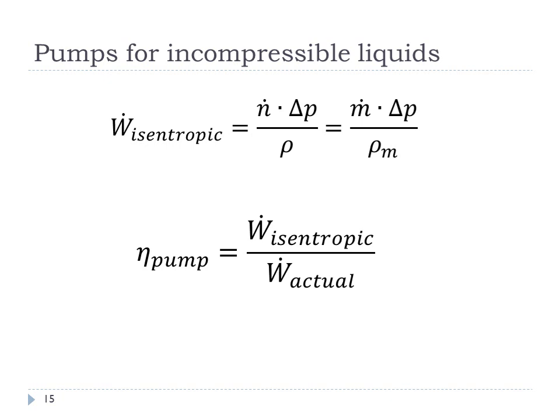For liquid pumps, since the liquid is incompressible, the isentropic work equals the flow rate times the change in pressure across the pump divided by the density. The actual work is the isentropic work divided by the pump efficiency. This is a simple but quite good estimate for pump work.